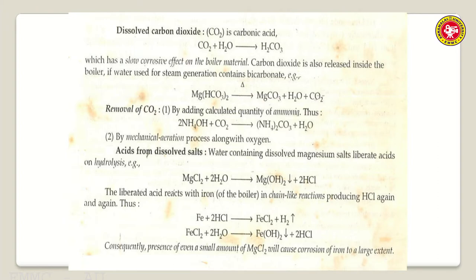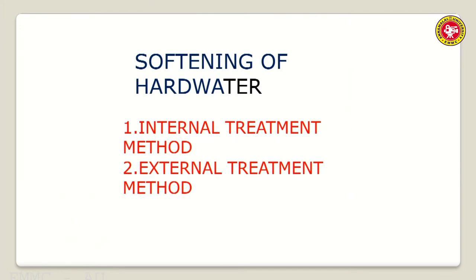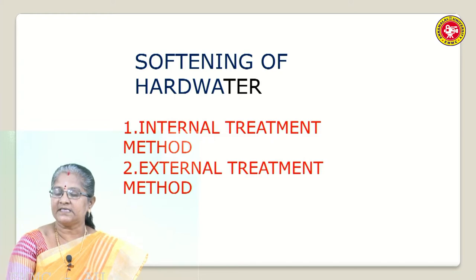The third reason for boiler corrosion is acid from dissolved salts. If magnesium chloride is present in hard water, it produces magnesium hydroxide plus 2HCl. This HCl reacts with the iron boiler body forming FeCl₂. FeCl₂ then reacts with water forming ferrous hydroxide plus more HCl, which attacks again in a chain-like reaction - continuously producing HCl and corroding the iron boiler body. Due to caustic embrittlement, boiler corrosion, scale and sludge formation, and priming and foaming, we must soften the water before feeding it into the boiler.